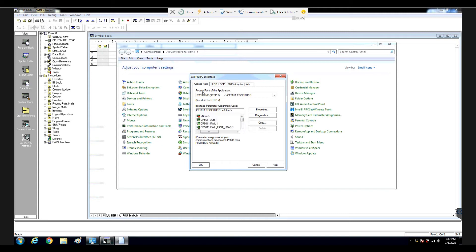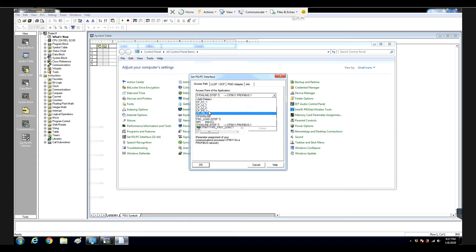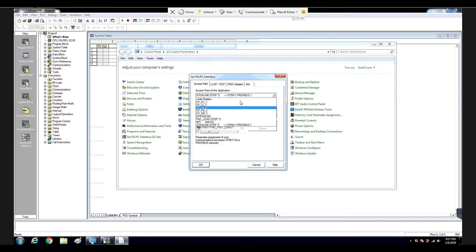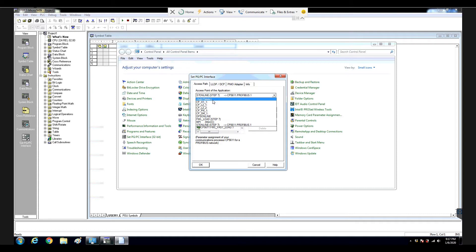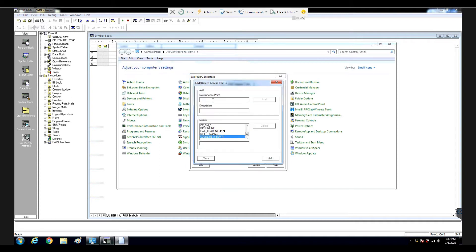From this access point of the application, if we compare with the previous one, it has a MicroWin heading to a card, point to a physical card. And this laptop doesn't have that. So, that means we need to manually create a channel, create an access point, and connect this access point to this physical card. Firstly, let's create an access point. And this access point, we can name what we want, but we better align with the software.